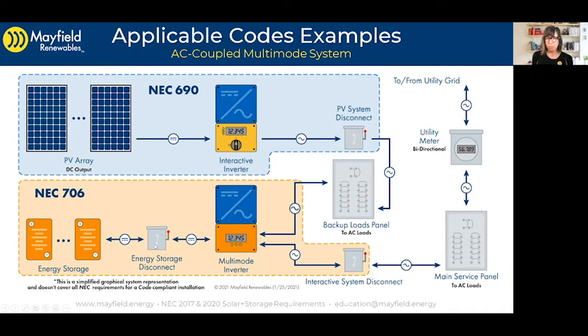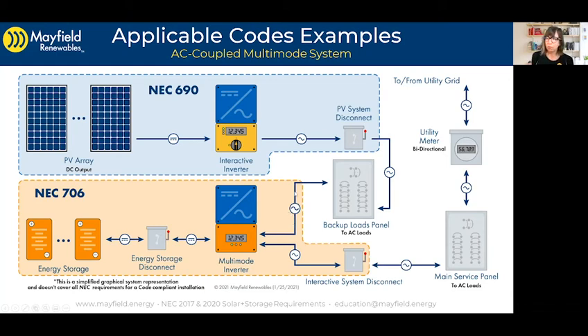People get a little concerned about the disconnect if it has to be on the DC side, because that can be tricky to accommodate in some installations. We may have to take advantage of remote control language — perhaps it's the remote control placed outside rather than the actual disconnect itself. With a fully packaged ESS, you may also be able to utilize an AC disconnect on the output circuit feeding the backed-up loads. If the goal is to shut down the circuits in the home, an AC output disconnect — because it has to be lockable open — might be able to do the trick. There's a little bit of confusion with the current version of the NEC, but if you think about the true intent of why that code section is there, you can come up with a way to satisfy it.